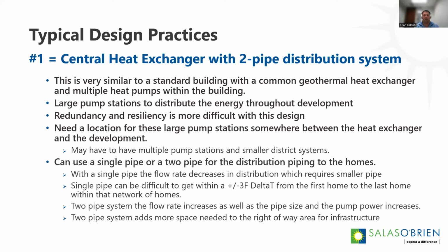The issue there becomes, number one, it gets very difficult to route the piping, because there isn't a community out there that's a square, so you're not going to be able to route piping effectively without crossing one another. And then it takes a large pumping station to distribute all that water throughout the development. It's also a little bit more difficult to design in some redundancy and resiliency. And then, where are you going to find a place in an existing neighborhood to put a large common loop field? And where's this pump house going to go?